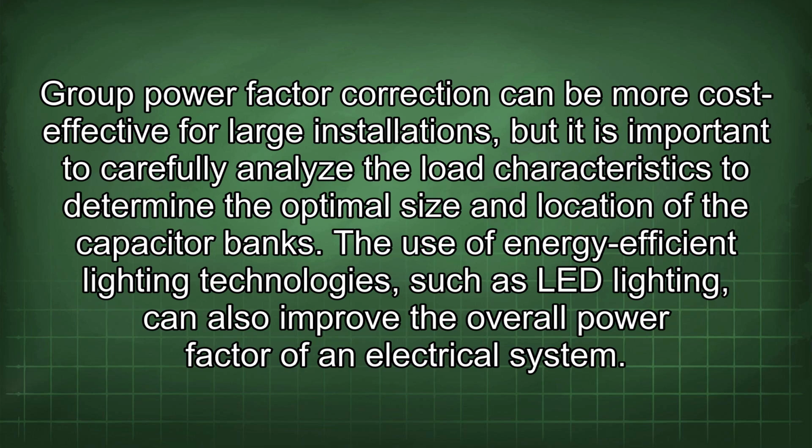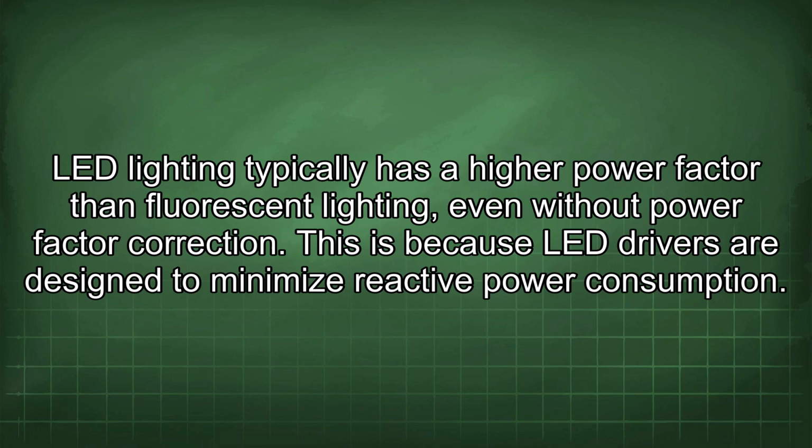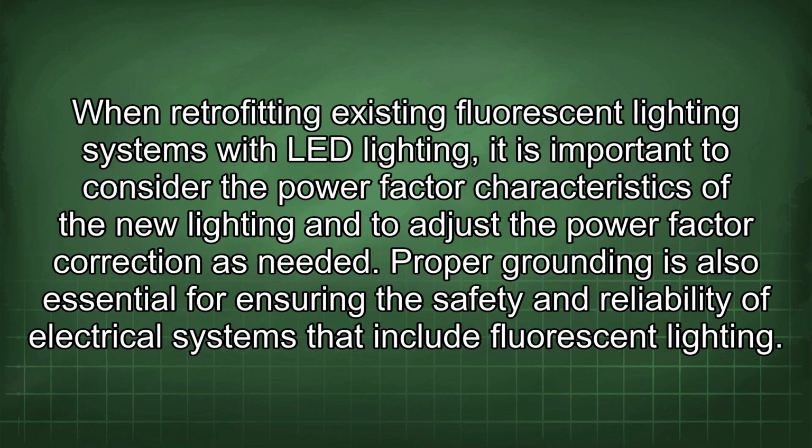The use of energy-efficient lighting technologies such as LED lighting can also improve the overall power factor of an electrical system. LED lighting typically has a higher power factor than fluorescent lighting, even without power factor correction. This is because LED drivers are designed to minimize reactive power consumption. When retrofitting existing fluorescent lighting systems with LED lighting, it is important to consider the power factor characteristics of the new lighting and to adjust the power factor correction as needed.